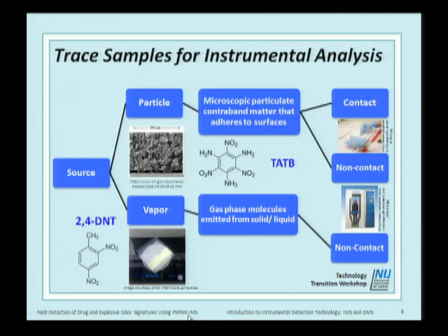Some of us have been in situations in the airport where we're placed in the people sampler, where they puff air all up and down our bodies in order to dislodge any potential particles that you may have from handling drugs during packaging or explosives. Those are directed into the analyzer to show whether there's presence of drugs or explosives. And lastly, vapor detection is obviously done with non-contact techniques, because again, it's coming off of the actual drug or explosive.